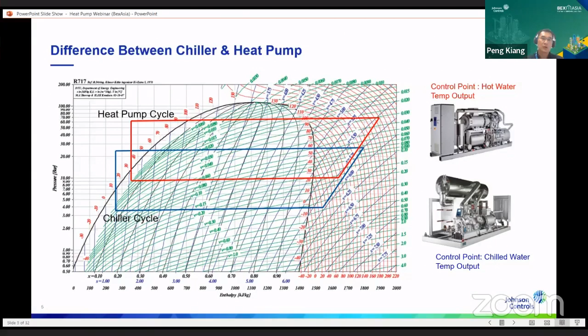Now, one thing to define about chiller efficiency, so heat pump efficiency, is COP. COP stands for coefficient of performance of a particular machine or chiller. It defines the useful work of a chiller or heat pump divided by the input power. So it's a ratio of the output energy divided by the input shaft power to the chiller. In terms of the ratio, the bigger the number, the more efficient it is to run a particular heat pump or chiller versus other kinds of machines.